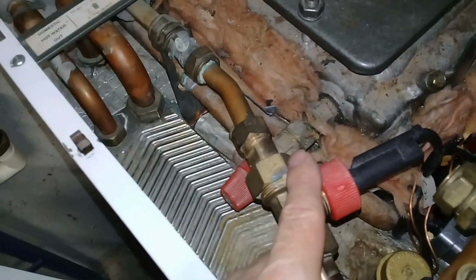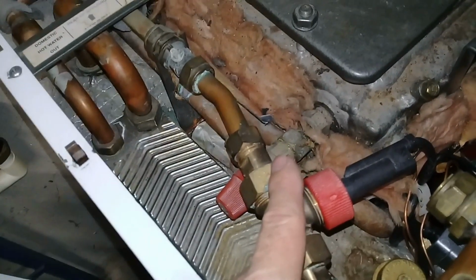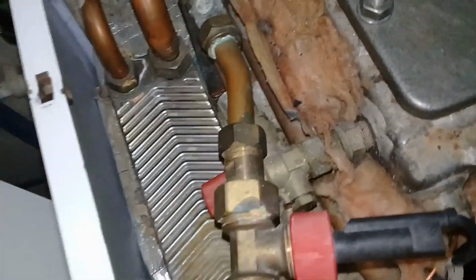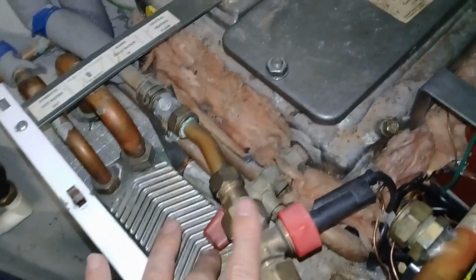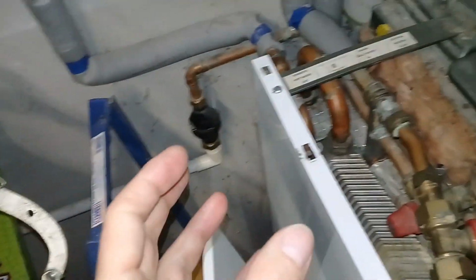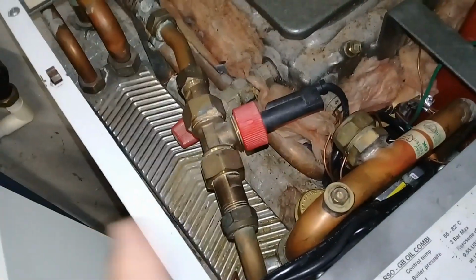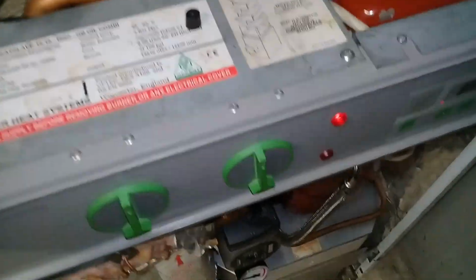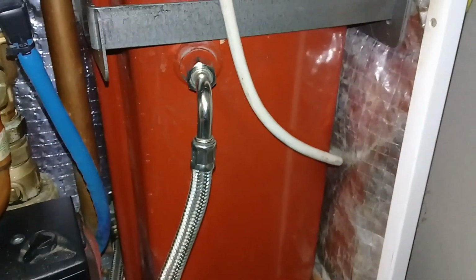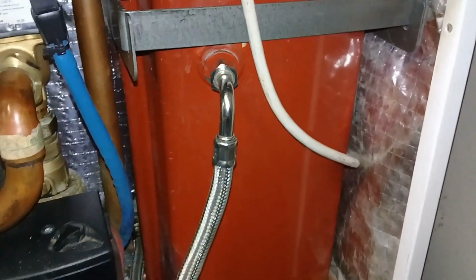So it's not the recommended method of releasing the pressure of the boiler. I think the best way is to do it via a radiator. Anyway, that's the typical behaviour: too much pressure in the boiler, this valve activating over 3 bar, and water coming out outside from the pipe. You can put a bag on the pipe to see if it has been doing that, because it shouldn't.